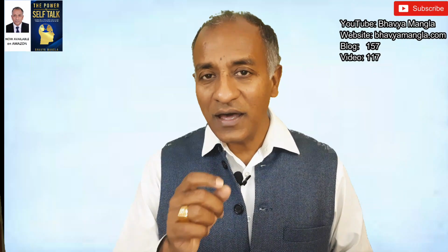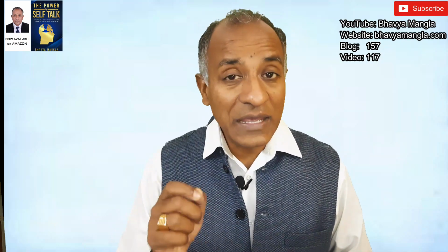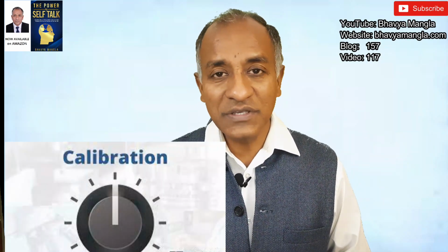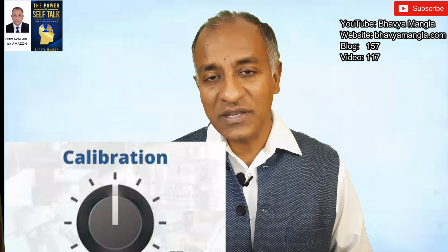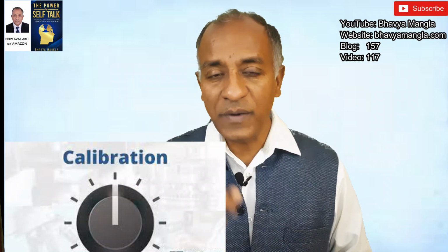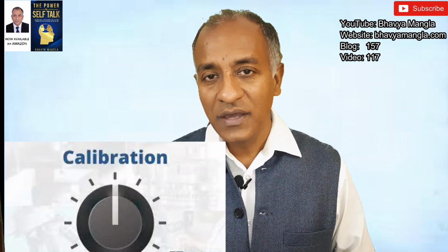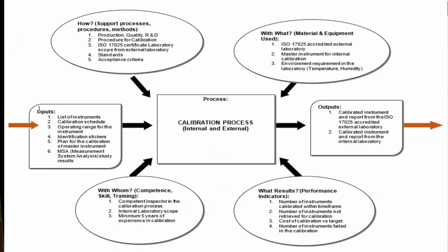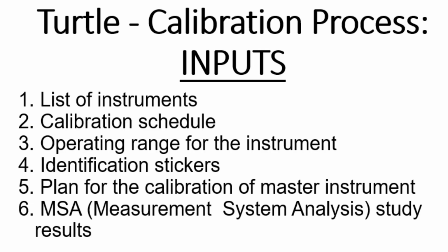So let's take a real example of the calibration process, and let's try to see how we can write each and everything for all the 6 different parameters with respect to a process. Now if you see in the picture, the calibration process is in the center, and when we start from the left, let's start from the inputs. So some of the key inputs are maybe the list of instruments, calibration schedule, operating range, identification stickers, and there can be many more inputs.